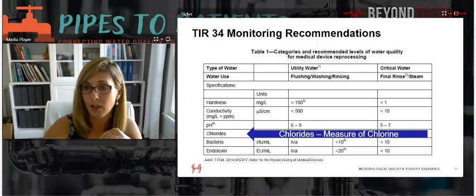Bacteria is measured by filtering the water and then providing nutrients for the bacteria to grow so that we can count these, as a colony forming unit, or CFU. The measurement is basically how many CFU are present in the aliquot we take during that testing, giving an indication of what's left in the water. And going back to what we talked about before, bacterial endotoxin measures how much bacterial endotoxin is still in the water using measurement tools like an LAL test.